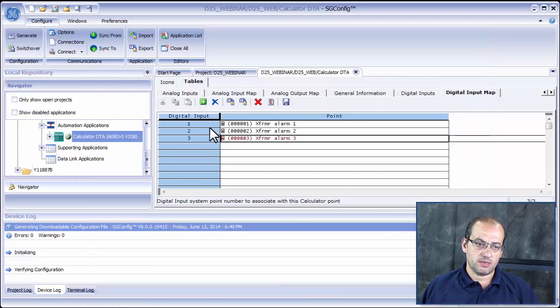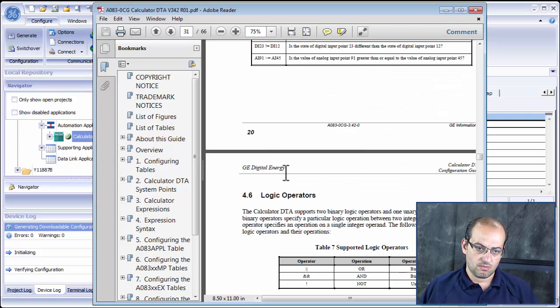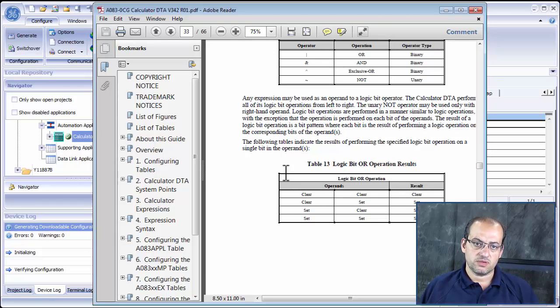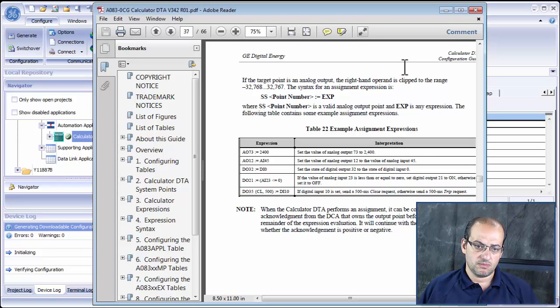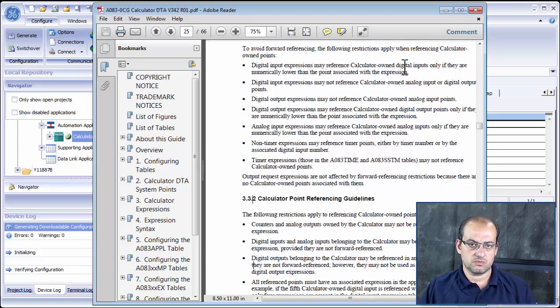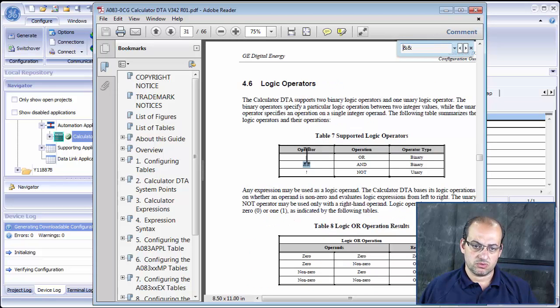In the Digital Inputs table we define the first expression as DI1 AND DI2. We can do a binary AND or a logical AND — we want a logical operation. So we have DI1 AND DI2. Once you're done, that's it for the Calculator configuration for those two points. Click Save.